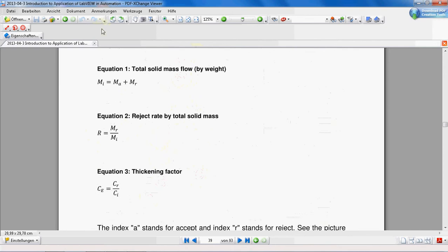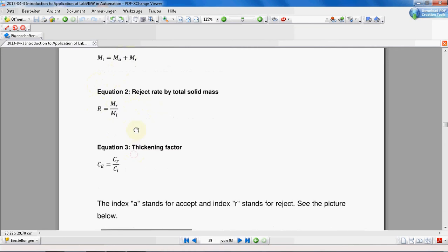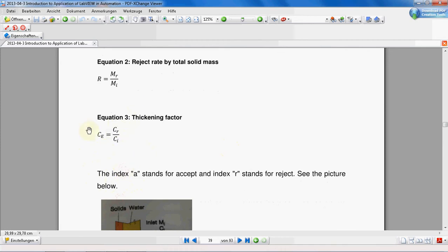You should be familiar with these formulas or concepts of the screening system in order to be able to make this program. These are very simple equations. If you are familiar with mass balance these are pretty obvious equations. It means inlet mass is equal to accepted mass plus the rejected mass. Reject rate is defined by dividing the reject mass by inlet mass. The thickening factor is defined as consistency of the rejected line divided by consistency of the inlet stock.